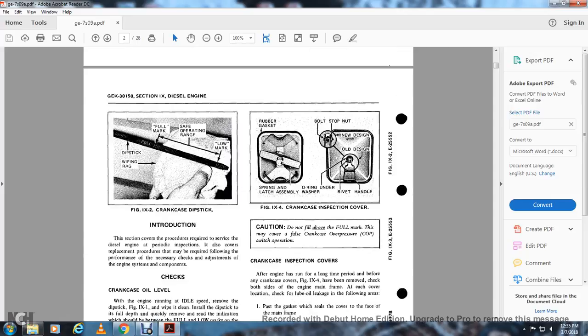Figure 9-4 shows the crankcase inspection cover with its rubber gasket, spring latch assembly, bolt stop nut. The new design uses an O-ring under the washer; the rivet handle and locking nut are also shown. Do not fill above the full mark, as this may cause crankcase overpressure or the pressure switch to operate.